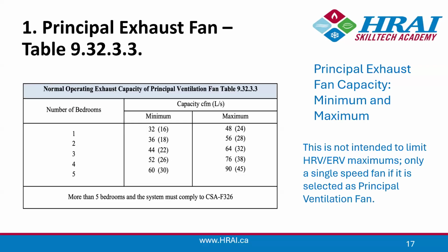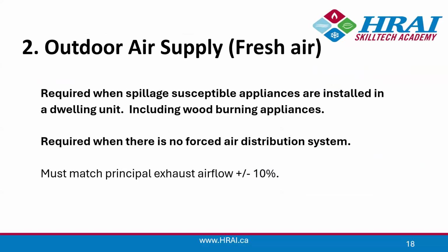As far as supply air goes, that's our main principal exhaust fan. That's a must-have. As far as our supply goes, that's a maybe. So we can depressurize with our exhaust fan if we prefer to, but we could also introduce supply. And I know some of you are saying, but wait a minute, don't we have to have an HRV? That's not 932, but yes, SB 12 does require that for almost every prescriptive package. So unless you're going to do performance modeling, or for some reason feel you don't need one and want to undertake the modeling, then of course that might be the case.